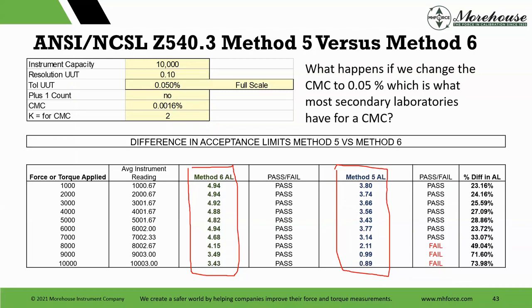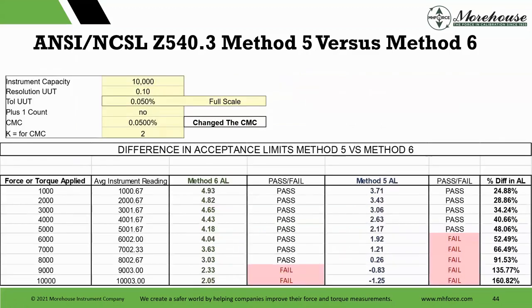However, if we look at these two, method 5 and method 6, and we change the CMC, this is looking at these contributors, the different contributors. Right here we're using dead weight. What if we change it to like 0.5? What happens? More fail on method 5, and on method 6, some start to fail. Why is this important? Because we've now applied a decision rule. We haven't just done simple acceptance, because with simple acceptance, honestly, almost any laboratory can apply something and pass it. Now, if they're accredited, they are required to report the measurement uncertainty, and the measurement uncertainty should not be greater than what they're calibrating, but there's still a whole heck of a lot of risk with that.